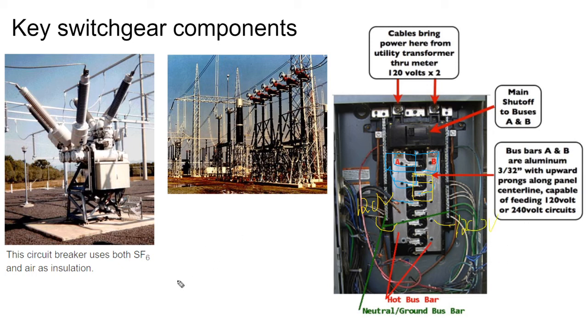This is a 120 volt leg, and this is a 120 volt leg that is 180 degrees out of phase. So when you have a sinusoid system with these 180 degree out of phases, they're going to maintain 120 volts to ground each. And if you connected two of them, it'll form a 240 volt circuit. So this 120 volt, 240 volt split phase setup allows you to use both 120 volt devices and 240 volt devices off of two 120 volt legs of power that come off of the same transformer.